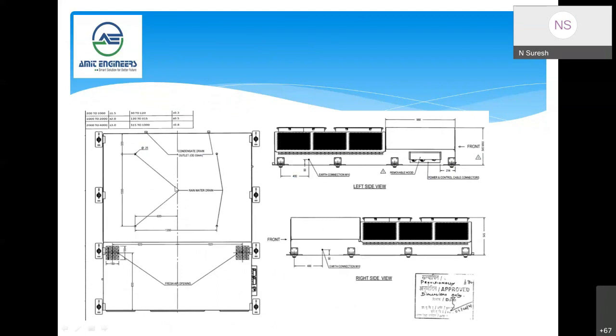This is basically the overall dimension of the unit, with some more clarity. There are 8 anti-vibration pads, condensation drains, and other than that, a few drains in the condenser area. Since the condenser area is exposed to the atmosphere, whatever water comes here will drain over there. But again, it is normal water outside. The water temperature will be normal to the ambient, so there won't be any problem.